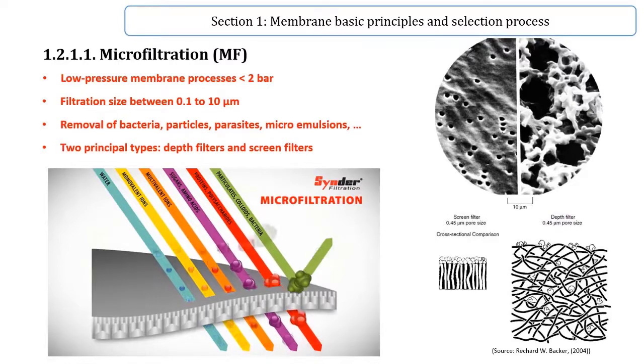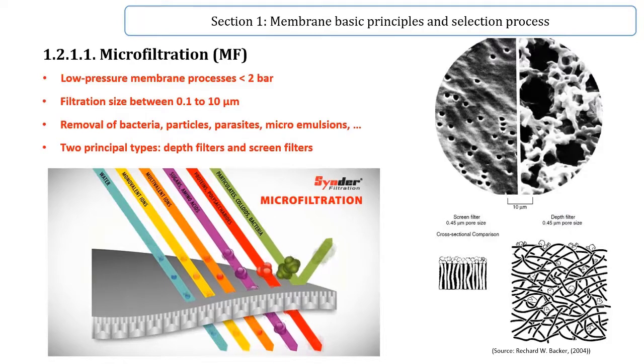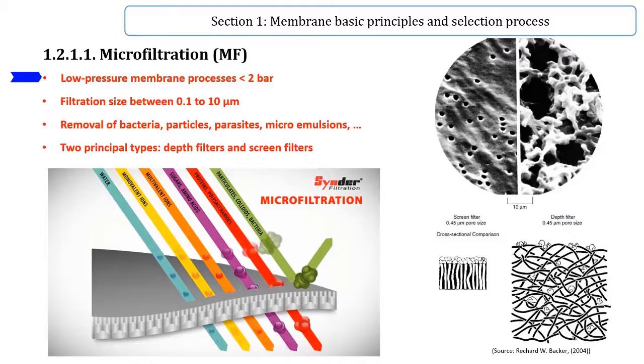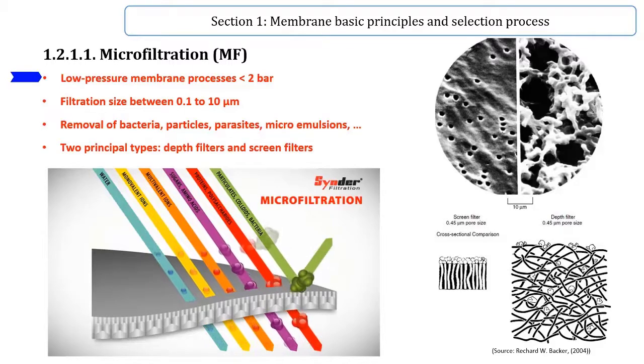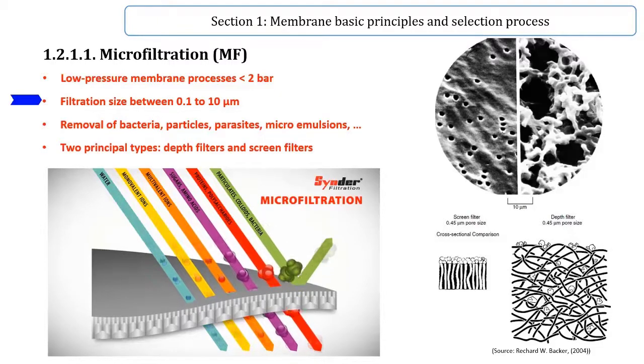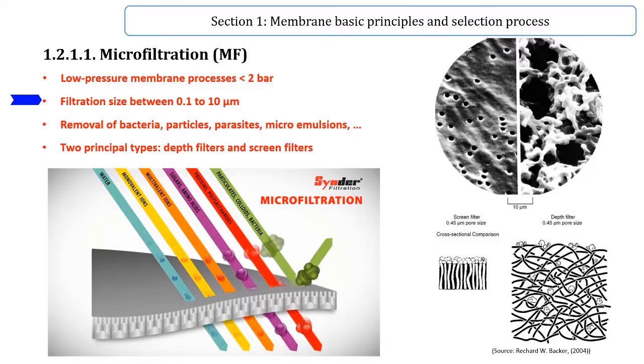Microfiltration is an important and widely used separation process. Among other membrane processes, microfiltration comes under the category of low pressure membrane processes due to the use of an applied pressure below 1 bar. Microfiltration refers to filtration processes that use a porous membrane to separate suspended particles with diameter between 0.1 to 10 micrometers.